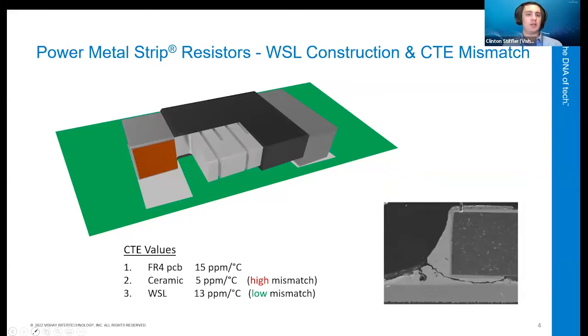One thing, especially with the construction and how we vary with the power metal strip versus thick film technology, I want to make sure to hit on, because it is large in automotive and EV applications: the CTE mismatch. As a material's temperature changes, the dimensions increase or decrease slightly as it expands or contracts. The temperature change can be a result of environmental change or caused by continuous or pulse applied power. In duty cycled or pulse applications, when power is switched on and off and on and off, it causes a repetitive heating and cooling, or expansion and contraction, cycle.